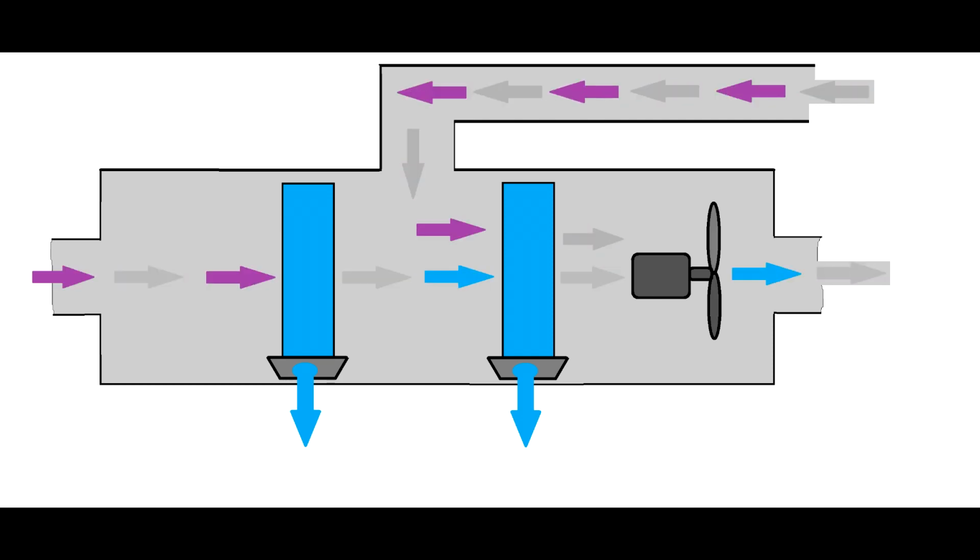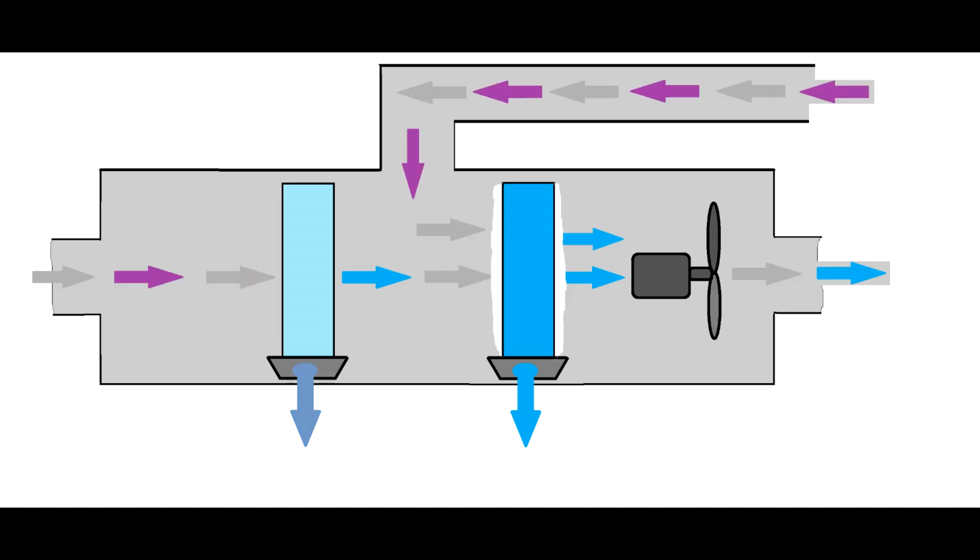Sometimes, unfortunately, some old design implies glycol that cools the heat exchanger, and that glycol runs on negative temperature. This example I'm going to give you is about a system which runs with glycol at minus 15 degrees Celsius. So the coil, the heat exchangers become very cold, and the cooler it gets, the more ice sits on the heat exchanger, and the more ice sits on the heat exchanger, the more restriction it will apply to the airflow until it can reach the point where there won't be airflow at all.